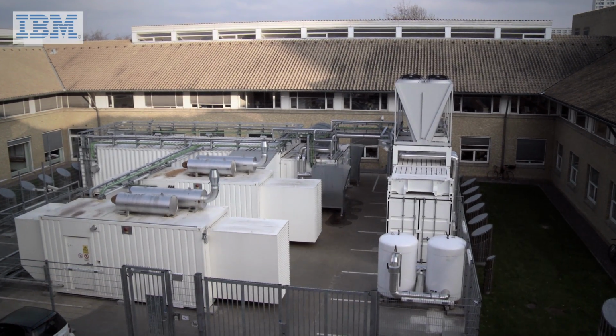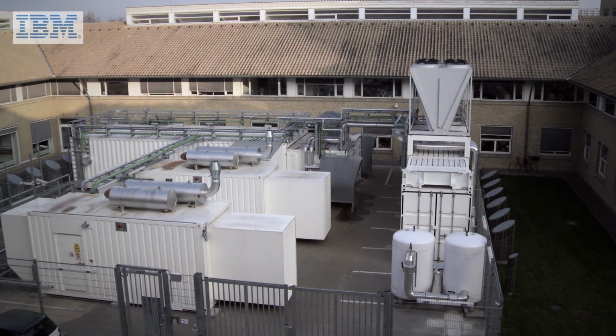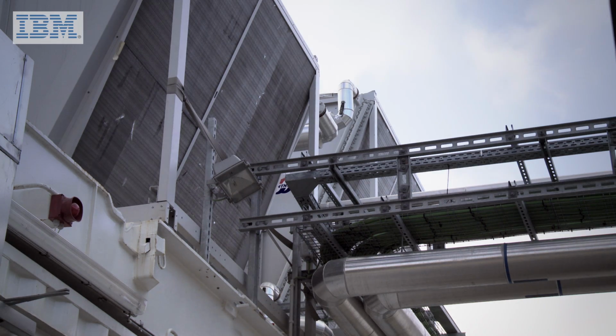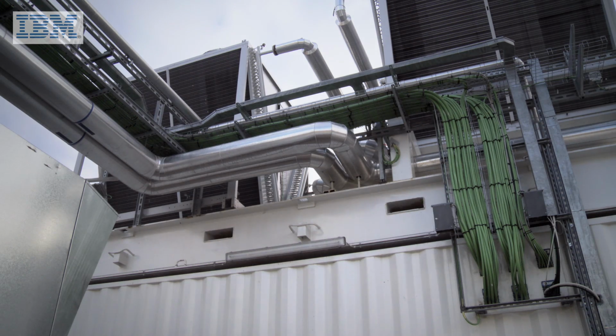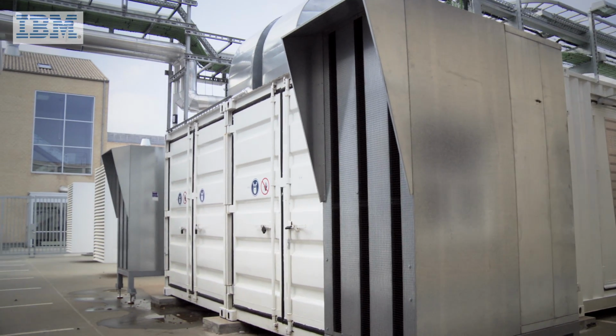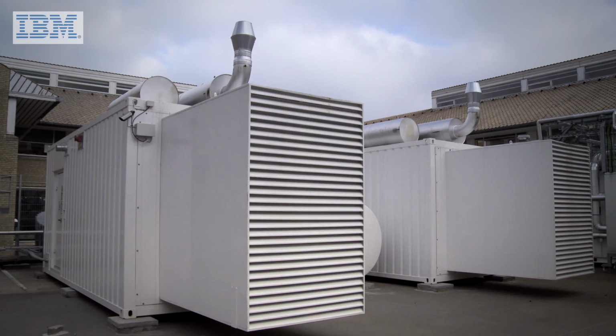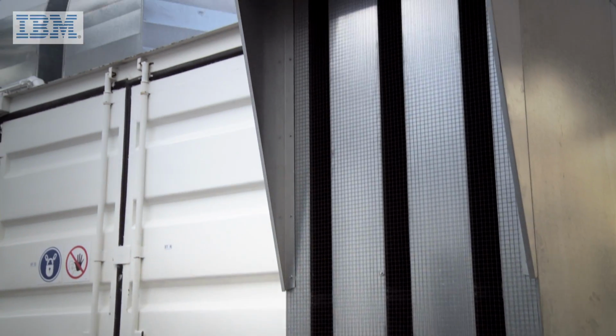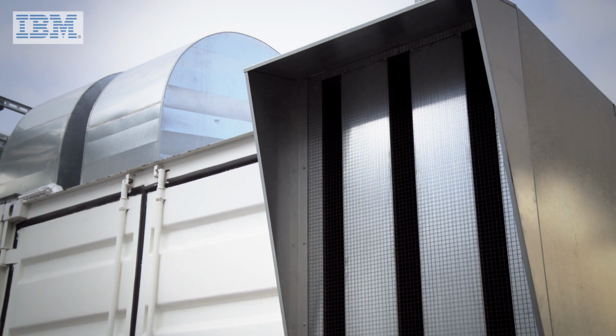This modular data center, as you may see, is made out of several ISO containers. Some are devoted to power and cooling, some for IT, and a few for the natural free cooling and also for the gensets. The IT modules behind me can host up to 30 racks with a total maximum IT power of 200 kilowatts. They are cooled by these natural free cooling modules, which are also N+1 redundant. And thanks to this cooling technology, we are able to run this data center in a very, very high energy efficiency mode.